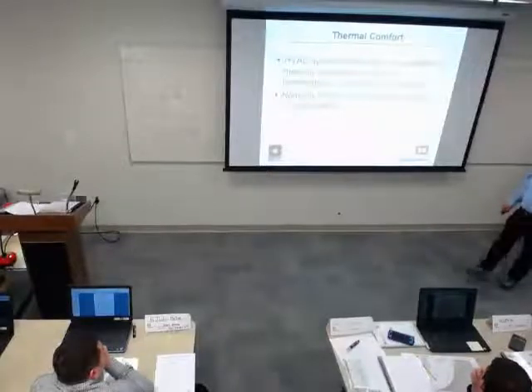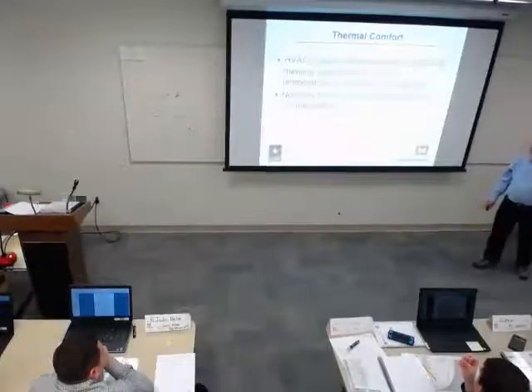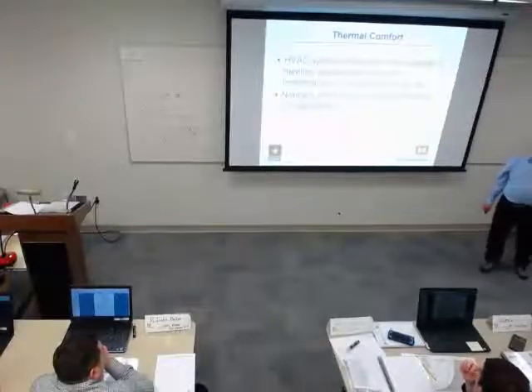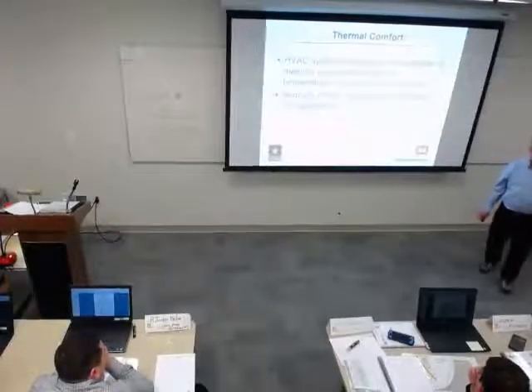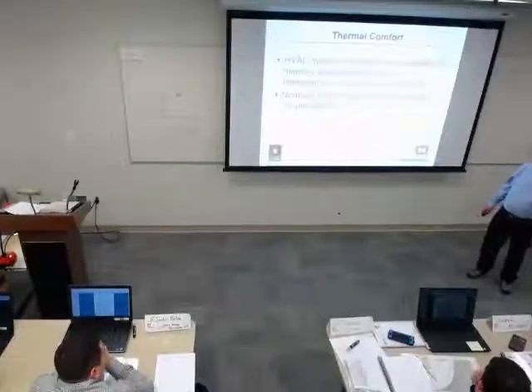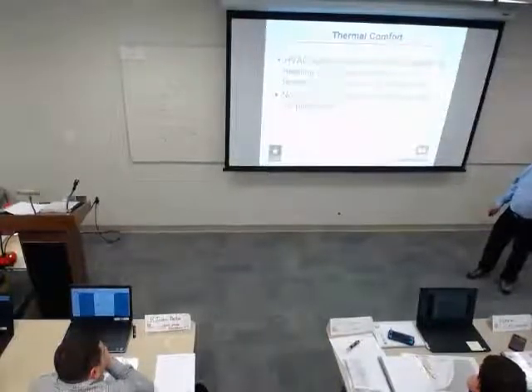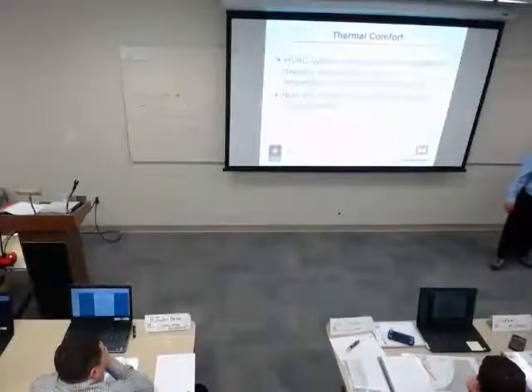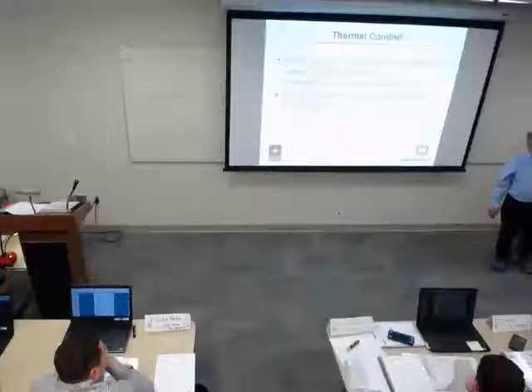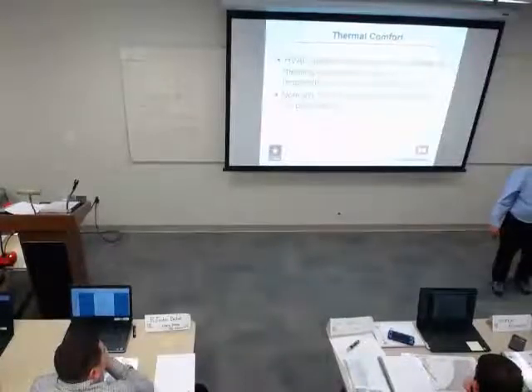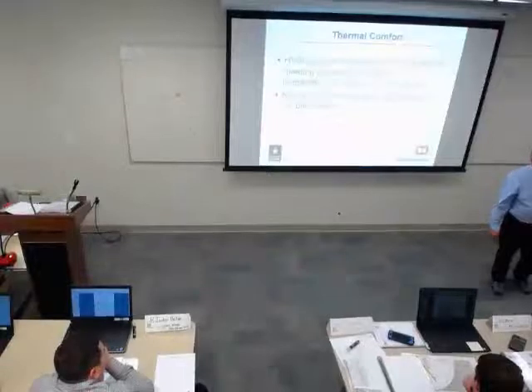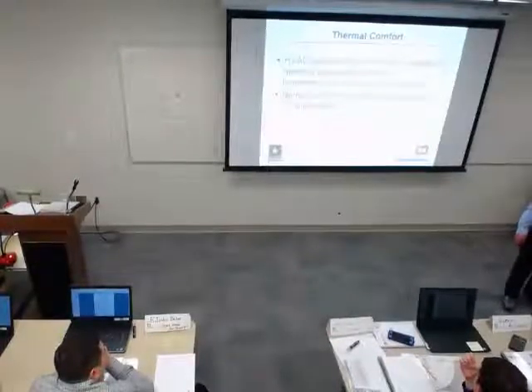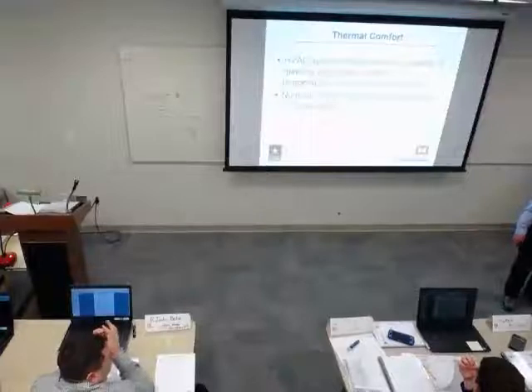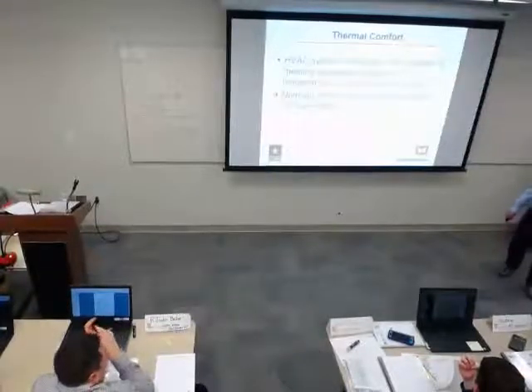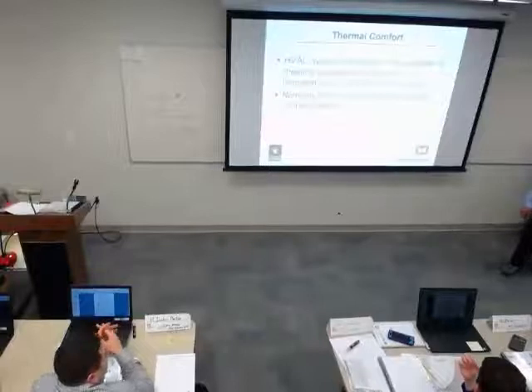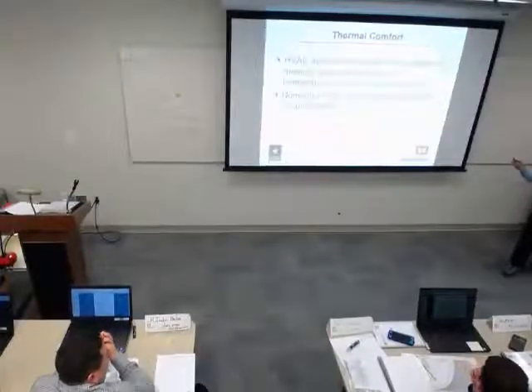The HVAC systems are designed to be capable of meeting the acceptable ranges of humidity and air velocity. And that's also part of the design, something we don't address in TAP, but it is part of the design. If we have troubles, that's something we'll check when we go to the space. And typically, we'll control one or two of those parameters. For cooling, we'll often attempt to control what we call the dry bulb temperature. We'll talk more about that in a little bit. And something we call the wet bulb temperature, or the dew point. For heating, generally we just look at temperature. There are some cases that will actually include humidity in that.